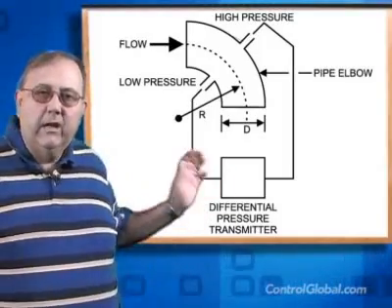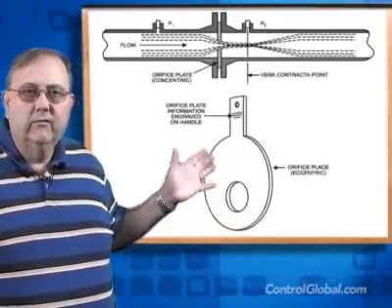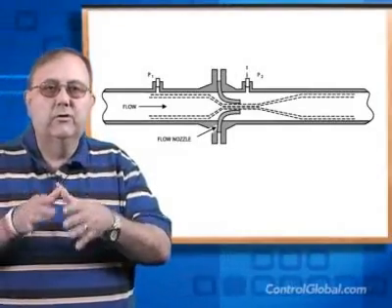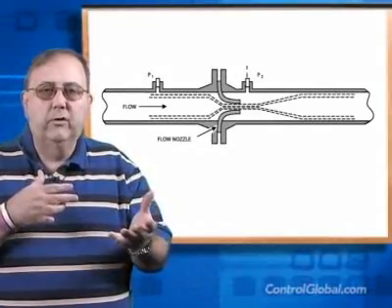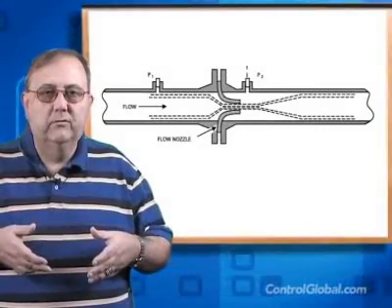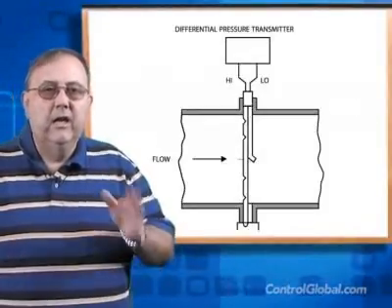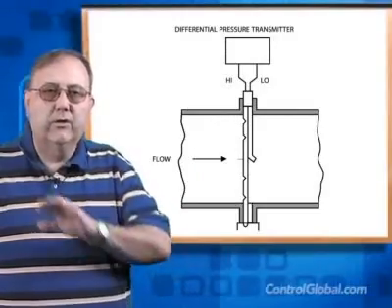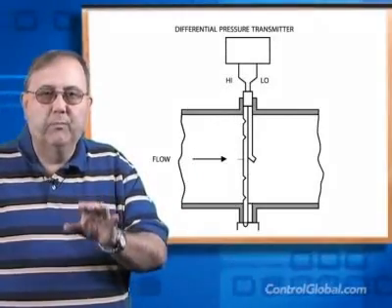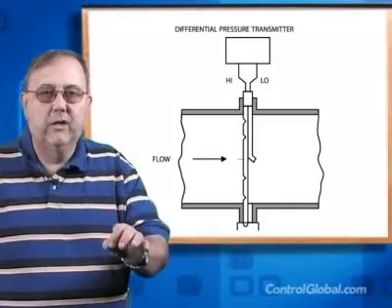There are many kinds of primary elements: orifice plates, venturi tubes, elbows, flow nozzles, low-loss flow tubes, single port and multiple port pitot tubes, segmental wedge and v-cone elements. Each of these elements is designed so that the volumetric flow rate is proportional to the square root of the pressure drop across the element.